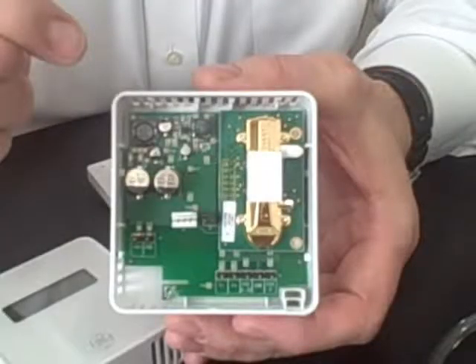Let's quickly look at our non-display Ventostat. This new modern enclosure includes our CO2 sensor and a temperature sensor. In fact, all of our new Ventostats have a 10K Type 2 temperature sensor as standard. The available outputs are current and voltage — a 4 to 20mA and a 0 to 10 or 0 to 5 — and you can select that on the jumper here.